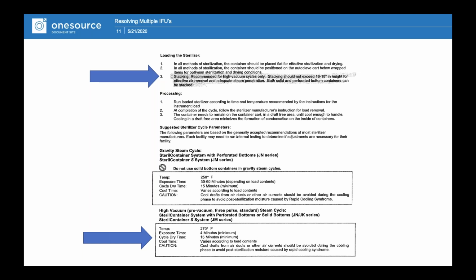If they're all Aesculaps and you look at the IFU here, they were looking for an answer of how many. Can I stack 1? Can I stack 2? Can I stack 3? Of course, the Aesculap IFU says neither. Stacking should not exceed 16 to 18 inches in height. So I'm getting instructions from the autoclave telling me don't put more than 20 16-pounders in there. But then the IFU here is telling me, oh wow, look, I could stack 16 to 18.